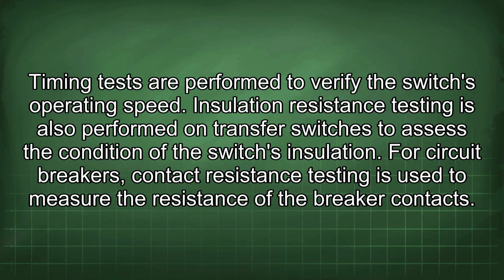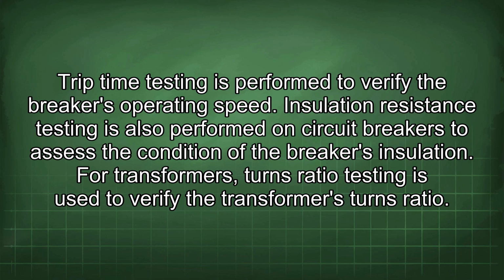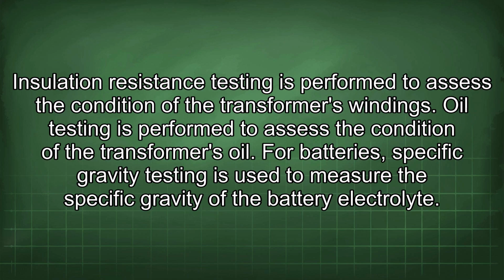For circuit breakers, contact resistance testing is used to measure the resistance of the breaker contacts. Trip time testing is performed to verify the breaker's operating speed. Insulation resistance testing is also performed on circuit breakers to assess the condition of the breaker's insulation. For transformers, turns ratio testing is used to verify the transformer's turns ratio. Insulation resistance testing is performed to assess the condition of the transformer's windings. Oil testing is performed to assess the condition of the transformer's oil.